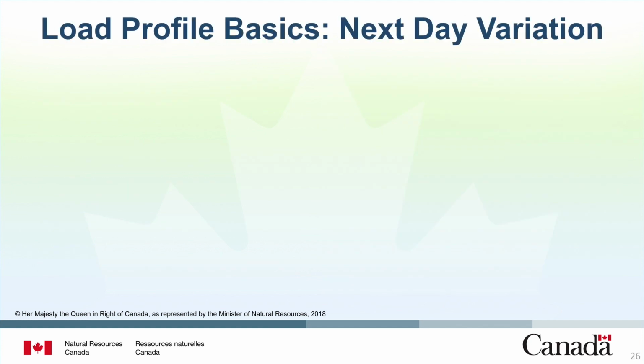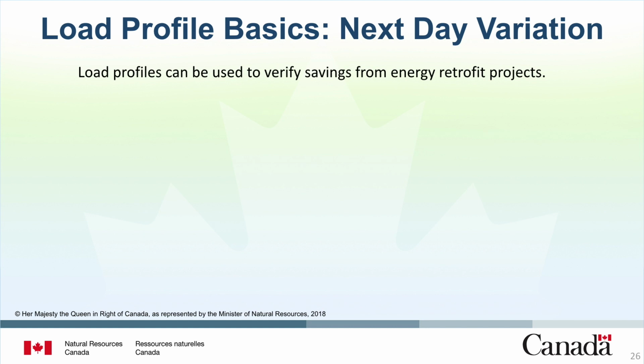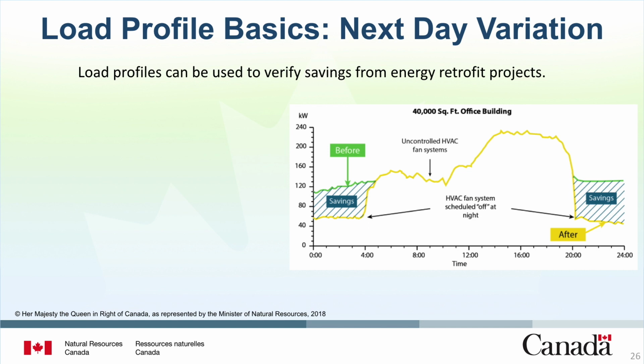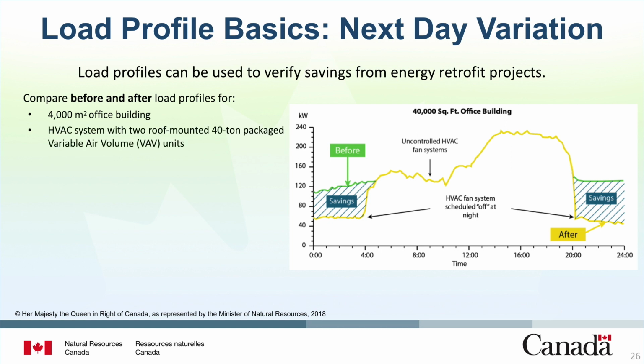Here is an example of how load profiles for one day, 24 hours, can be used to verify energy savings from a retrofit project. Load profiles can be used to verify savings from energy retrofit projects like the controls upgrade represented in this image. The graph compares the before and after load profiles of a 4,000 square meter, 4-story office building that uses an HVAC system consisting of 2 roof-mounted 40-ton packaged variable air volume units with perimeter electric resistance fan-powered VAV boxes.